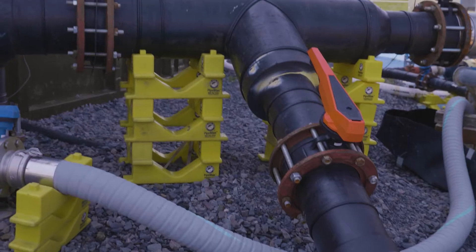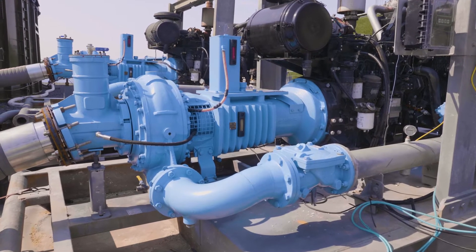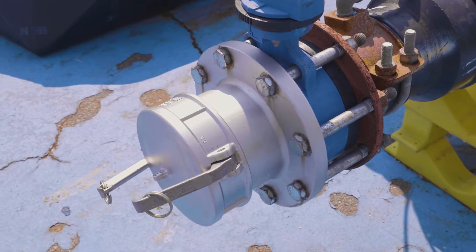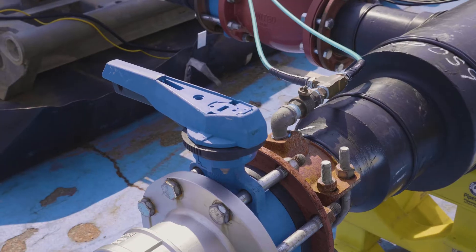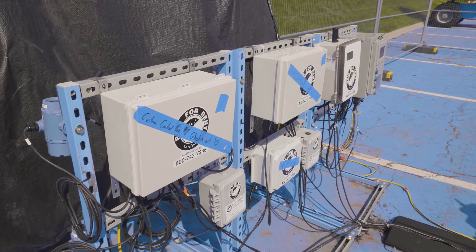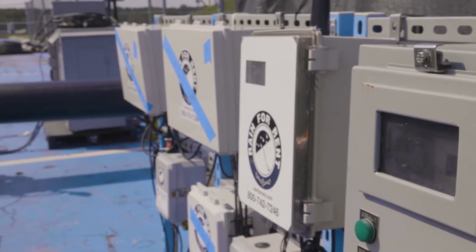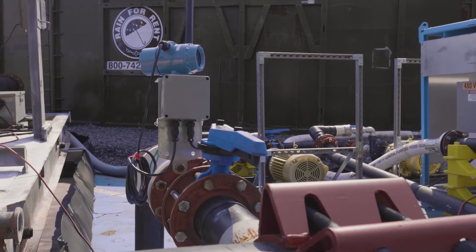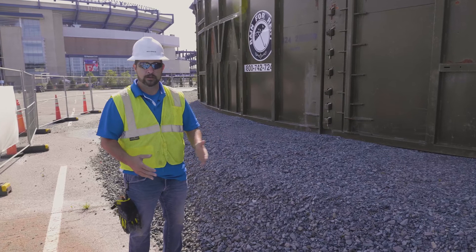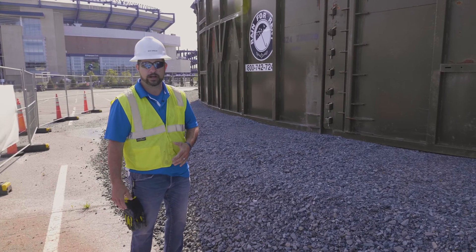The HH-160I handles fire demand only if it should arise. The pumps are remote capable, so if there's a water main break they can shut the pumps off without worrying about water going everywhere. We turn the tank over 10% per day using the electric pumps, using custom control boxes with specific times and parameters for start and stop. At night we refill the tanks at 10% back up to a specific level based on pressure transducers, inline flow, and automated valves.